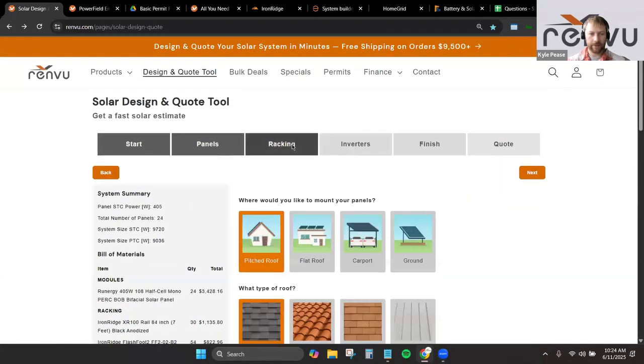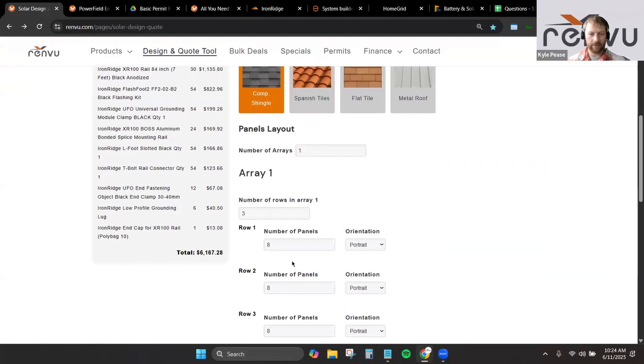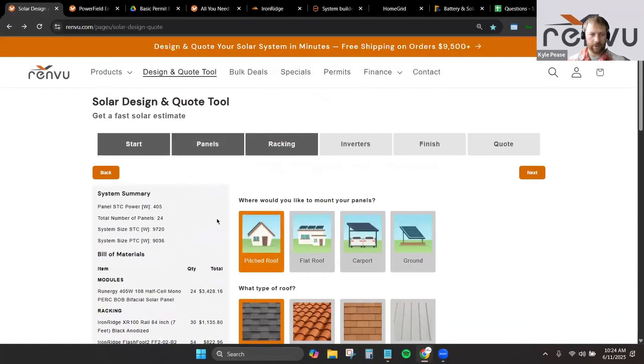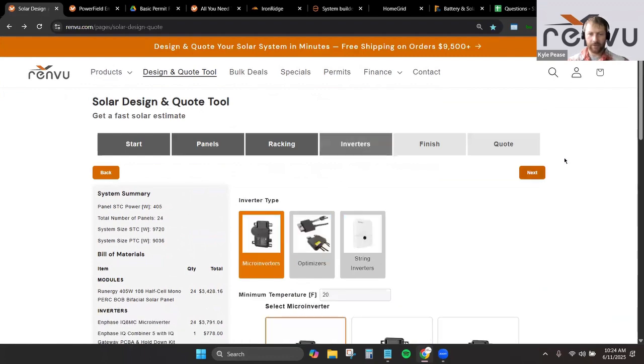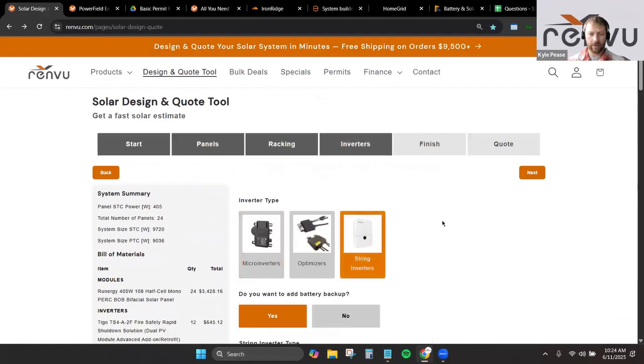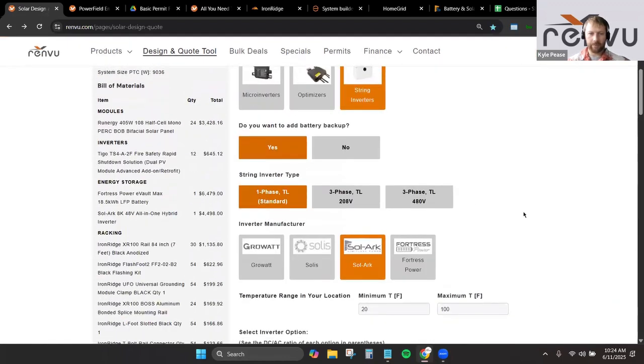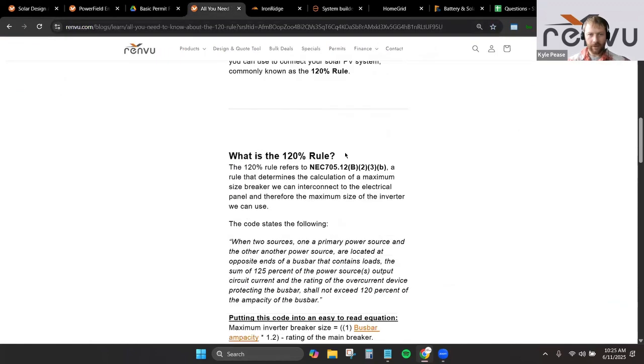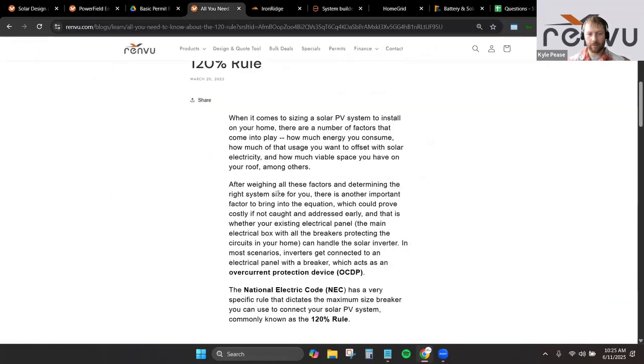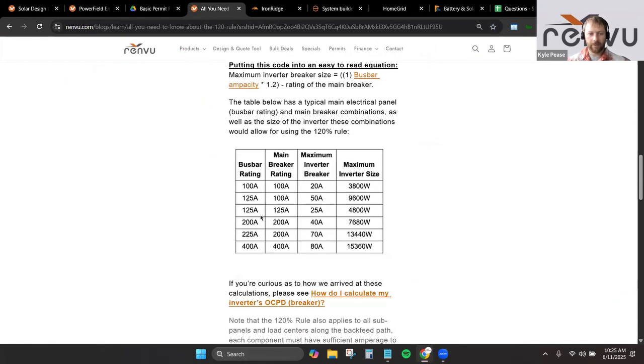So I'm going to jump back to the racking and we're going to leave it at 24 modules. So it's a 9.7 kilowatt DC system, which is a decent size for a fully loaded 200 amp main panel. Under the 120% rule, we have an article on our website about this here that goes over, depending on your main breaker and your bus bar rating, how many amps of solar you can back feed through that 120% rule.